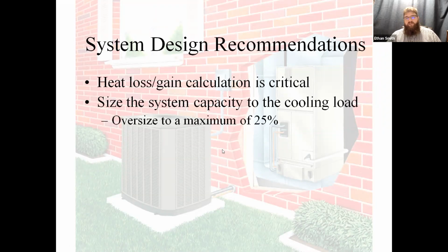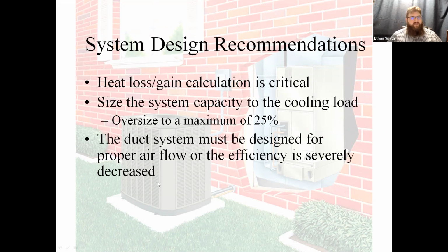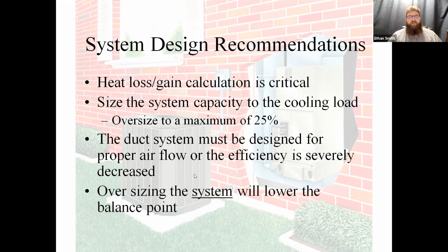We only oversize to a maximum of 25%. That is assuming, of course, that the ductwork will handle that oversize. Again, ductwork, guys. If you thought airflow was important in air conditioning, it's doubly so in heat pump operations. You're going to have serious problems. Oversizing systems will lower system balance points if you're going to use the system balance point to control the system. So be aware of that.